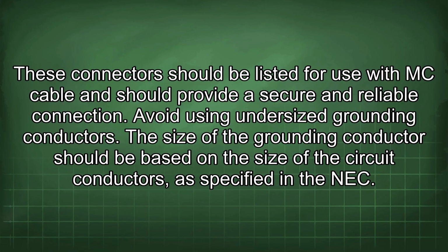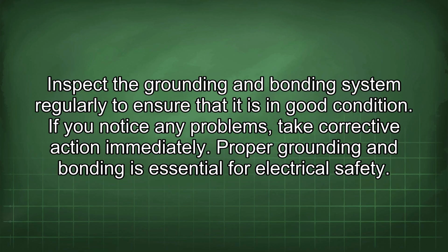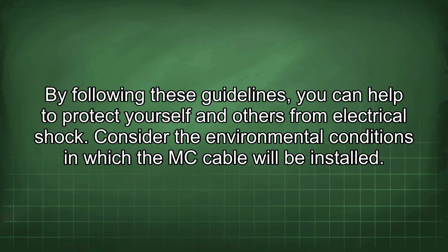Avoid using undersized grounding conductors. The size of the grounding conductor should be based on the size of the circuit conductors, as specified in the NEC. Inspect the grounding and bonding system regularly to ensure that it is in good condition. If you notice any problems, take corrective action immediately. Proper grounding and bonding is essential for electrical safety. By following these guidelines, you can help to protect yourself and others from electrical shock.